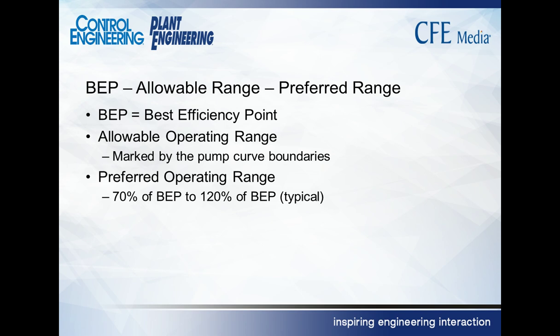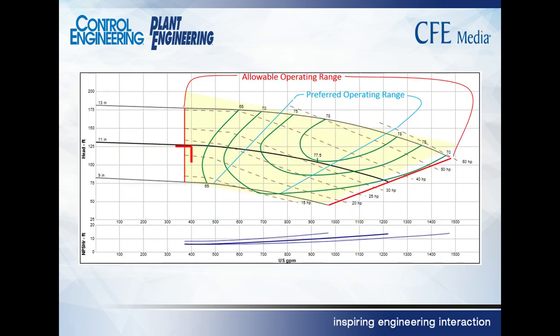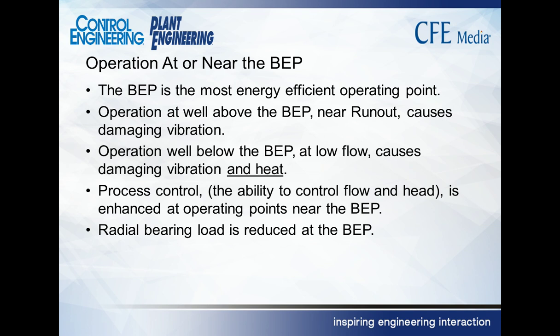The head's going to be constantly changing as the sump level changes. So there is a range across which the pump will operate. We like to keep that range within the allowable operating range, and under no circumstances do we want to get outside of the allowable operating range. I might have misspoke. We want to stay within the preferred operating range, and we definitely don't want to exceed the allowable operating range, as illustrated here. The effect of being outside the preferred operating range is a significant loss in efficiency and some other bad things that happen with the pump that we'll talk about here in just a minute.